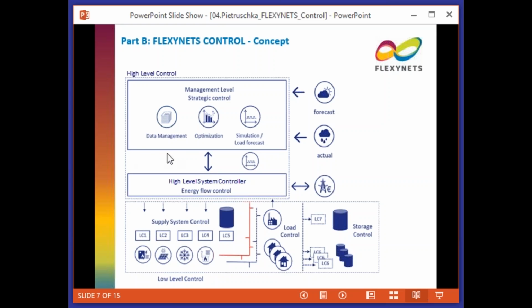But this can also happen on a more strategic level. If I integrate electricity prices, gas prices, and weather forecast data, I know what my demand will be through predictions, and I can develop a better strategy for how the system could be operated to maximize, for example, renewable sources in the network. This is all done at the management or strategic control level, from which the high-level control gets operational schedules for each device, which are then transferred to the single sub-devices that try to follow these schedules as long as possible.